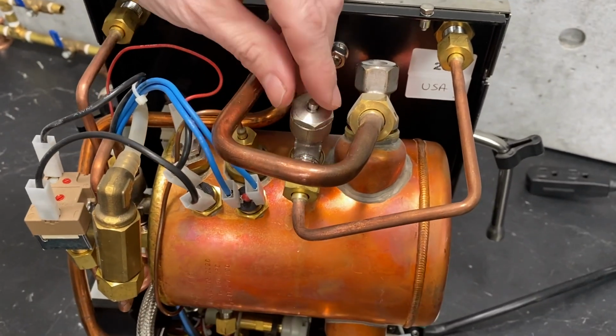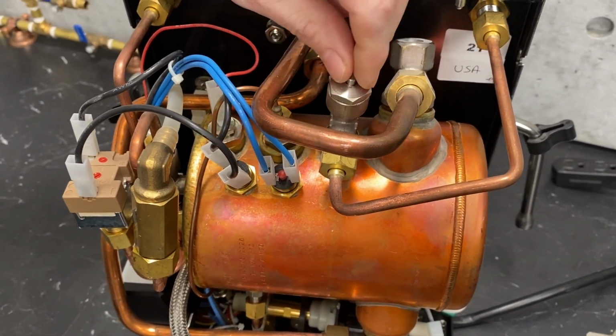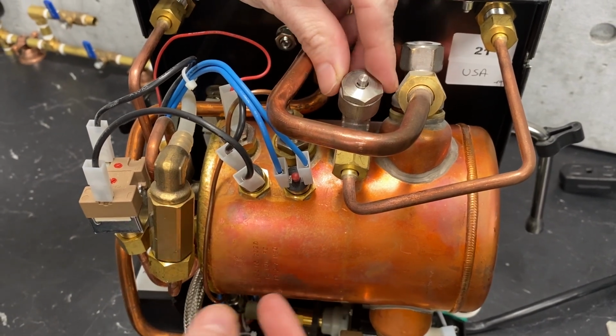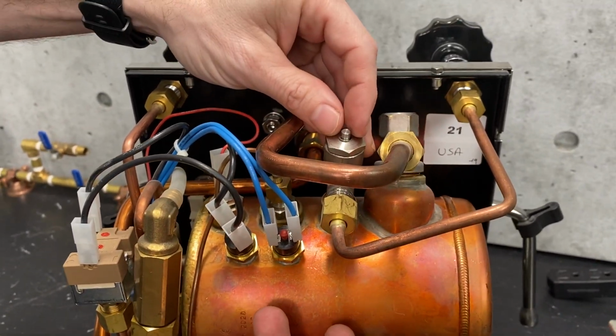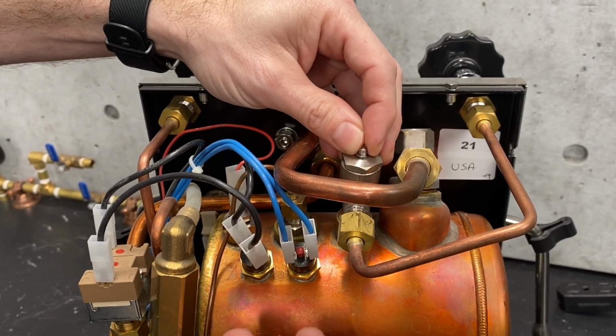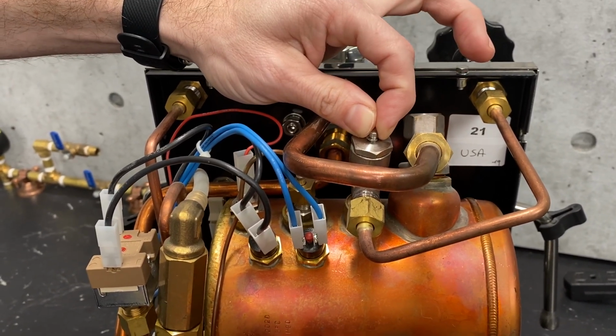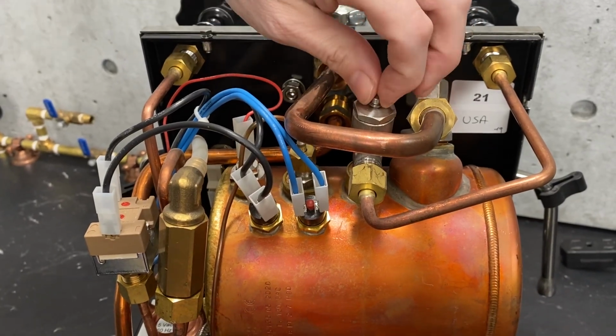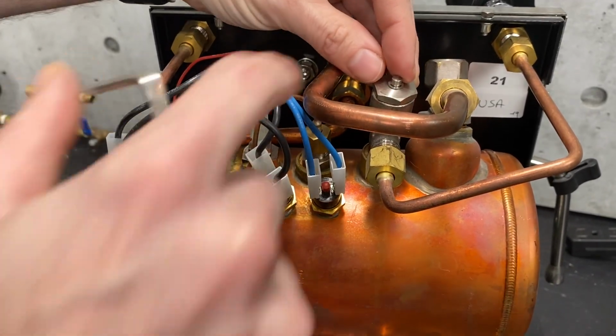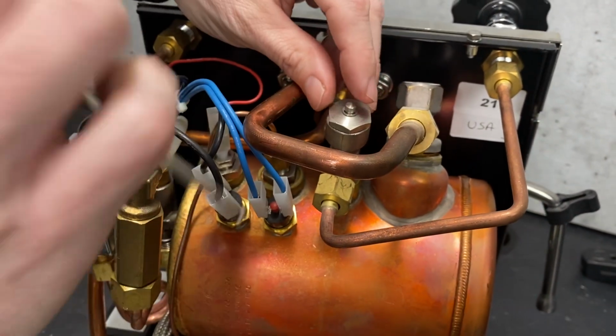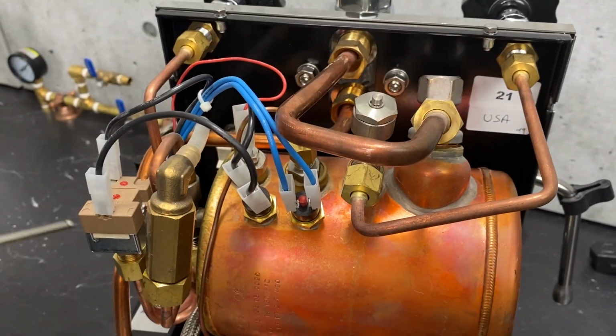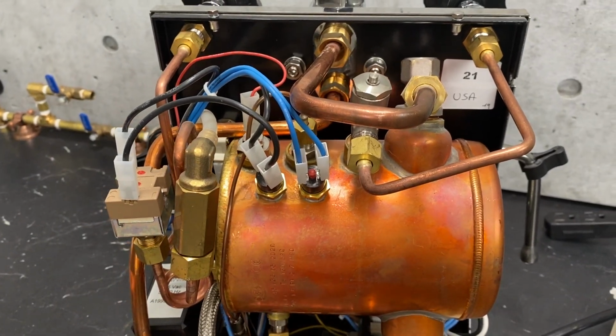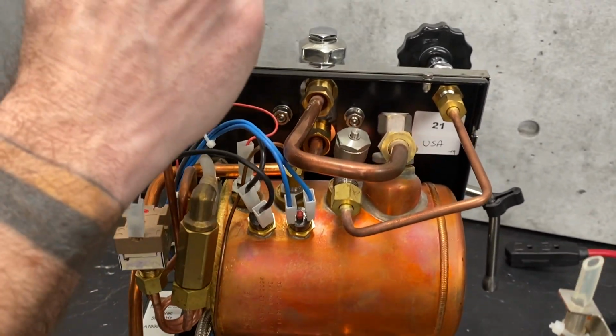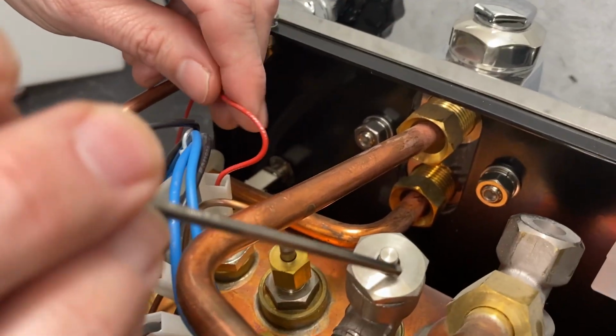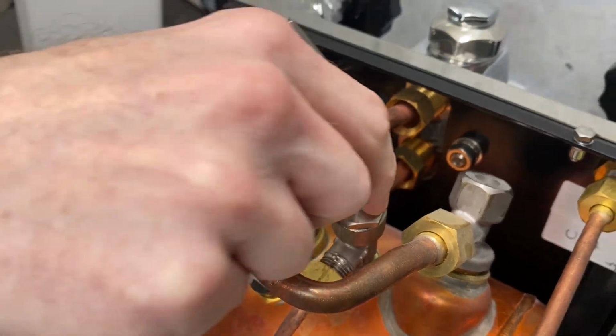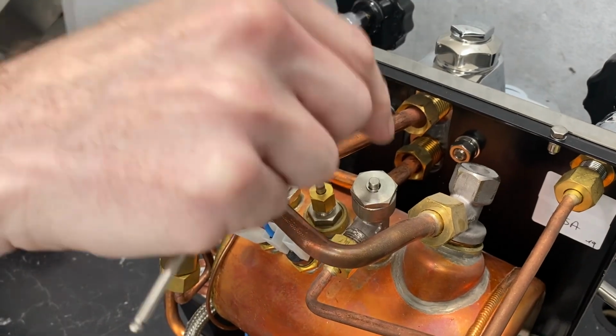Right here we have the vacuum relief, anti-suction, non-suction, however you want to call it. Basically, as the boiler is heating up, it is releasing some pressure. As that pressure builds, this will pop up all the way. So this is a pretty simple mechanism. It's just a little piston with an O-ring around it and a little clip holding it in place. Pretty easy to service. We'll be having a video on that shortly. Come over to here. Oh, I will actually point out with the vacuum relief, when you're first heating your machine up, there we go.